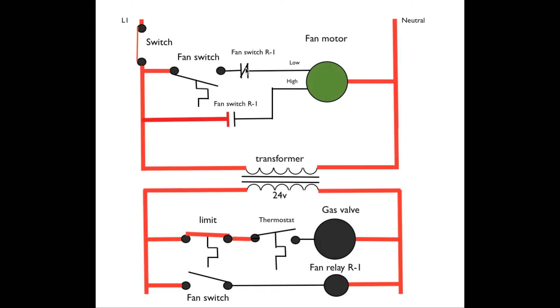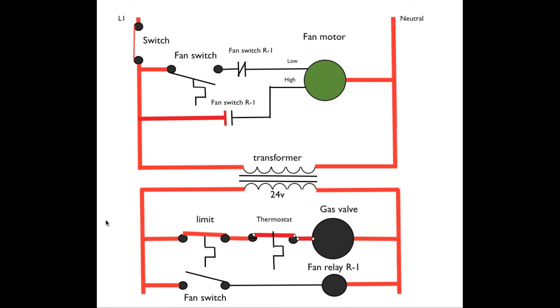So let's go ahead and sequence this thing. Let's do a sequence on a call for heat. Okay, what we've done is we close this thermostat. The limit's already closed. Power passes through the limit, through the closed thermostat, to energize the gas valve. That's going to start the gas furnace operating.